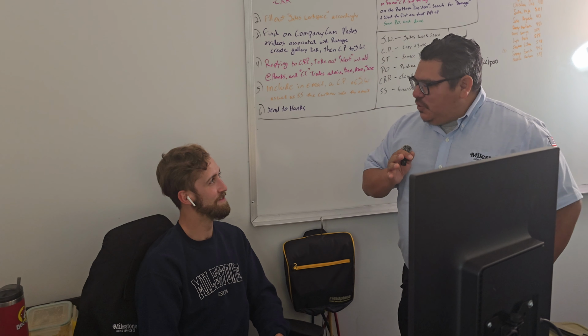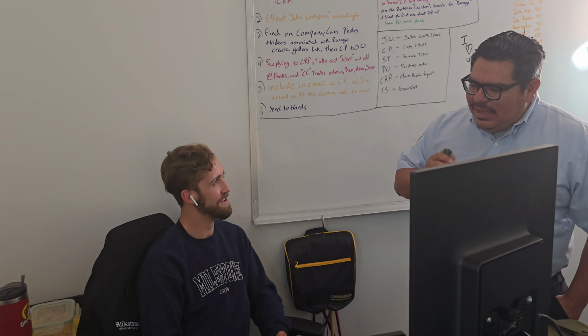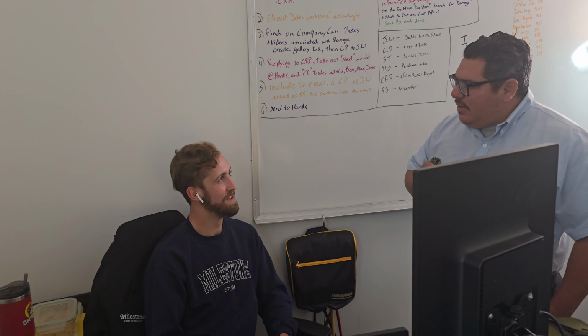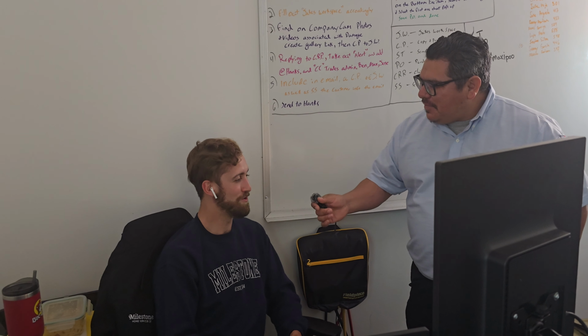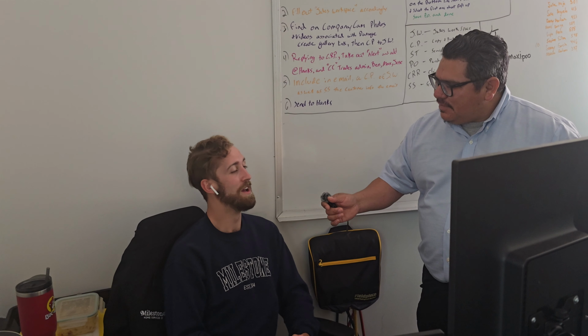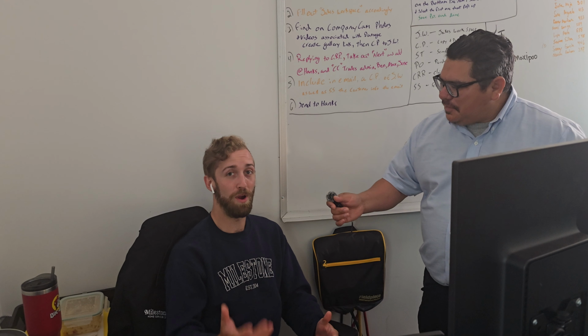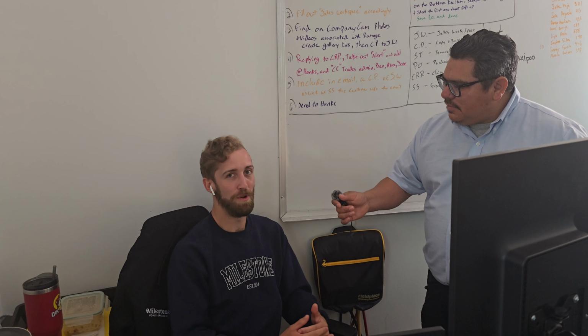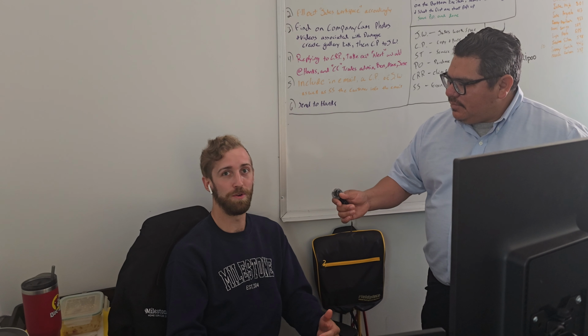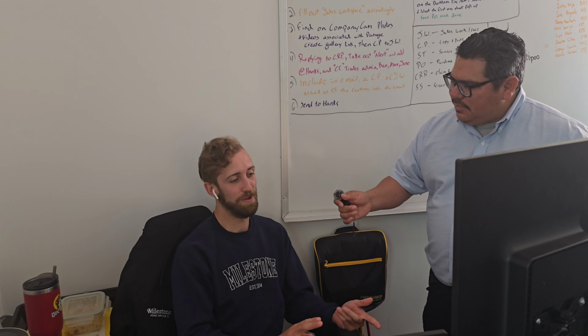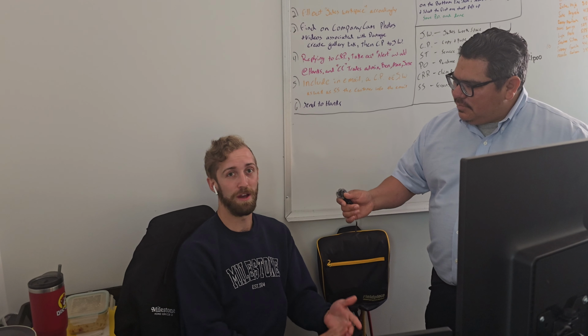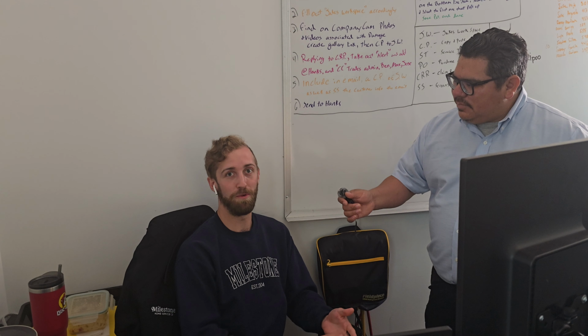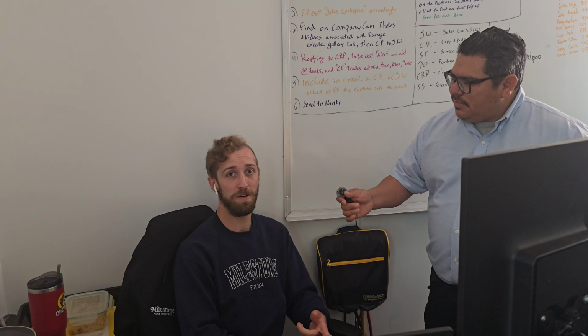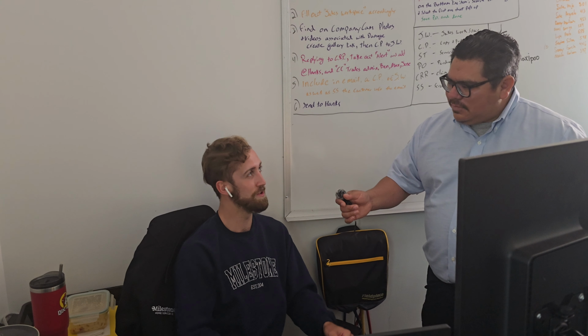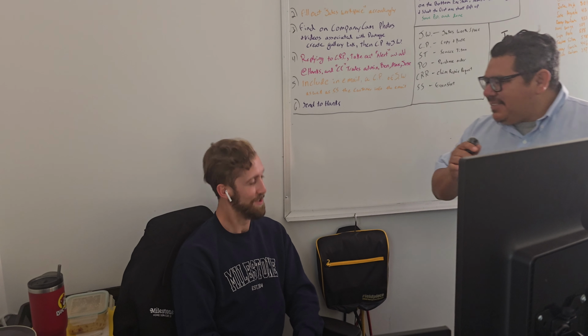So I have 2 questions for you, Max. Yes, sir. How important is static pressure to the unit, and why? Static pressure is extremely important to a unit. Not only does it verify that you have proper return and proper supply, but it makes sure that we're pulling enough airflow across the coil to get a good temperature split, and make sure the unit's not over-condensating and pulling out the correct amount of moisture from the house. So that will have effects with humidity inside a home, as well as the comfort level for our customers. Excellent. Thank you, Max. You're welcome.